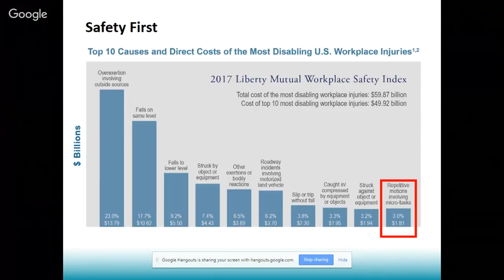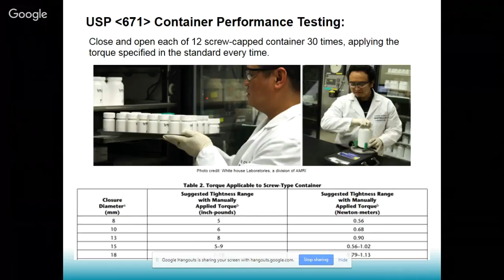One, as it relates to the USP 671 container performance testing standard, the standard calls for closing and opening 12 screw cap containers 30 times. And if you have a number of batches, a number of different container sizes that you have to deal with, then obviously 360 samples for each package design, that's a large number of containers. So you want to make sure that the operators are, instead of using a manual tester, using an automated device. The risk with the repetitive motion injury is that when you test these large batches, your wrist and shoulder motion, the joints can create a stress or strain on them.